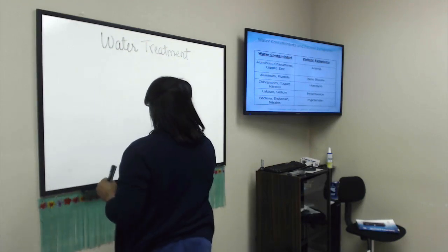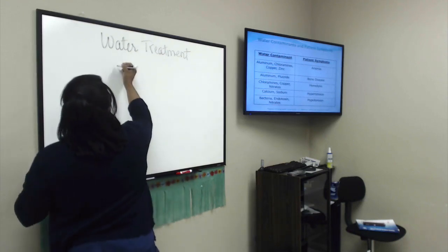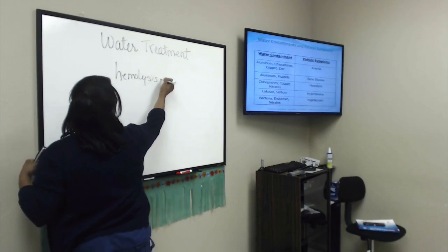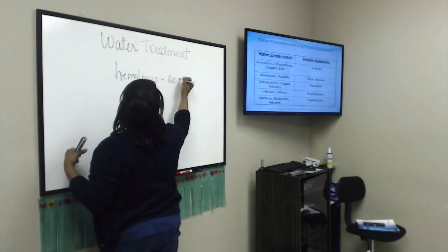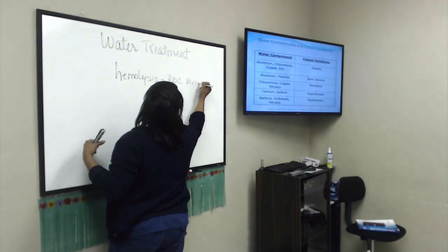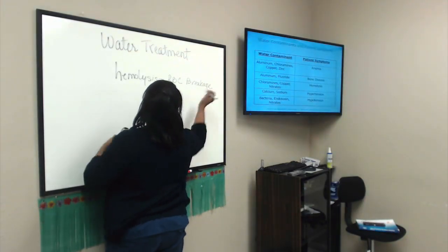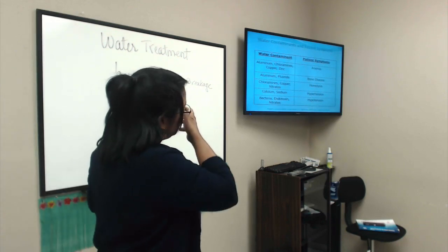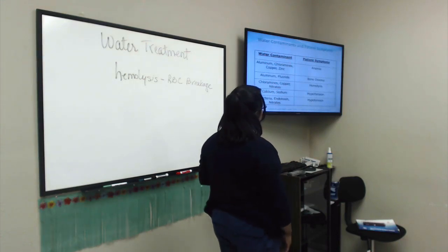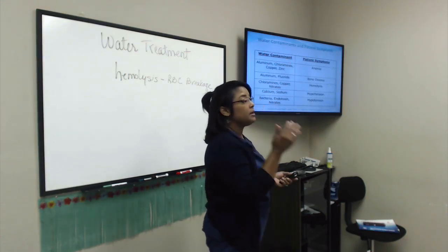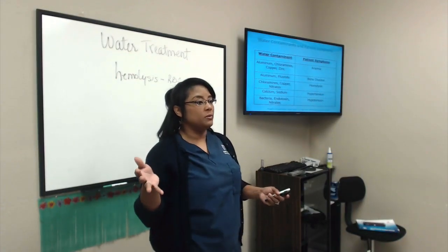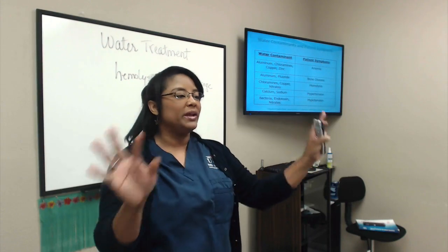And remember that hemolysis is red blood cells breakage. Red blood cells breakage. We don't want that. Calcium and sodium can cause hypertension. Bacteria, endotoxin, nitrates can cause hypotension, okay? So let's say there's a breakthrough, God forbid, but let's say there's a breakthrough.